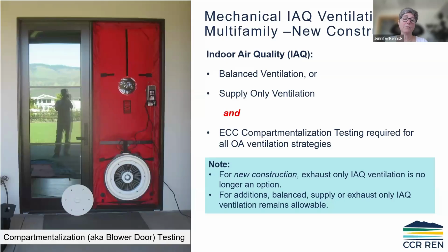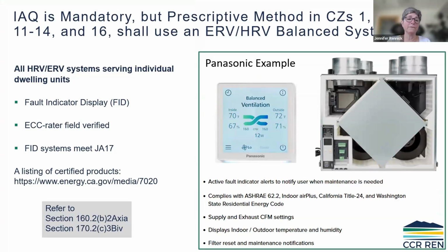for multifamily housing projects, you either have to do the balanced ventilation or the supply only ventilation. And so that harkens back to that slide I showed you in the single family. In addition to that, you have to have compartmentalization testing by your ECC rater, otherwise known as a blower door test. And basically what it means is that for new construction, the exhaust only IAQ ventilation fans are no longer an option. So having outside air introduced into the space via balanced ventilation or supply only ventilation is mandatory.